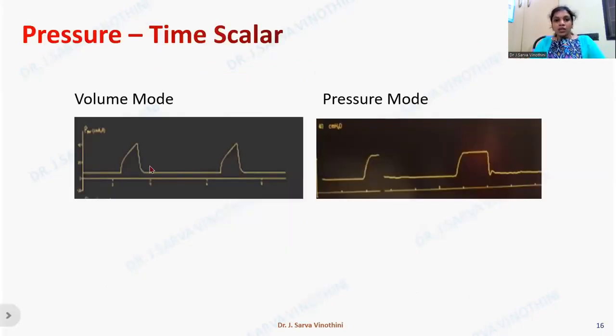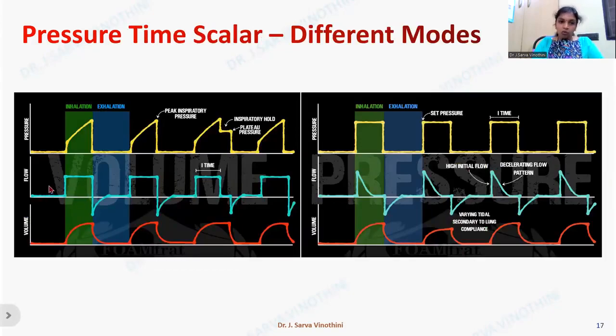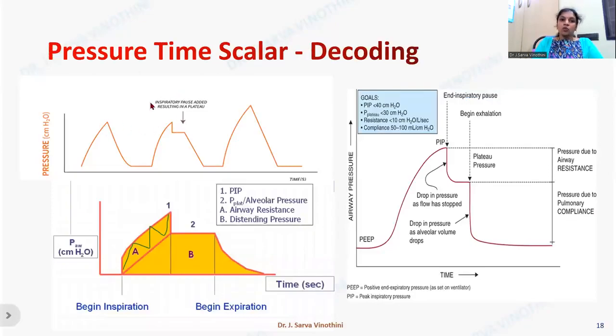In the volume control mode, the pressure-time scalar has a shark-fin appearance, whereas in the pressure control mode it has a square waveform because we have determined the pressure. The flow-time scalar in volume control mode shows a square wave pattern, while in pressure control mode it shows a descending ramp waveform. When we press the inspiratory hold button in volume control mode, we see a plateau pressure appearing in the pressure-time scalar. The peak pressure is followed by the plateau pressure on pressing the inspiratory hold button.